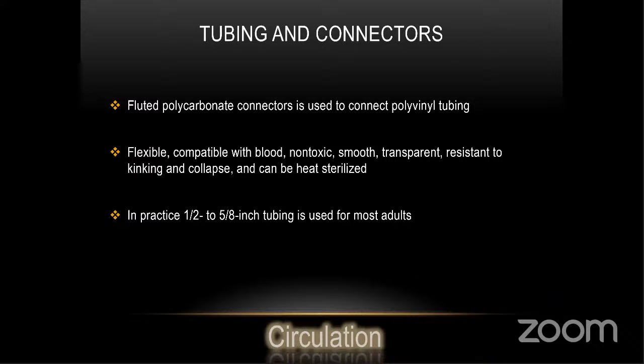The various components of the heart-lung machine are connected by polyvinyl tubing and polycarbonate connectors. The polyvinyl tubing is flexible, compatible with blood, non-toxic, smooth and transparent, resistant to kinking and collapse, and can be heat sterilized.